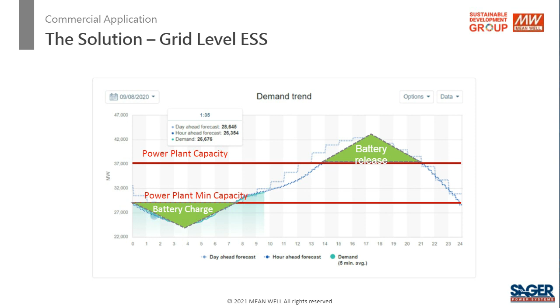During the power plant minimum capacity period, when energy is not used as much, it's able to charge the battery to refill it for the peak release during peak demand. There are two terms: the battery charging at the bottom is called valley filling, and at the peak, during release, that's called peak shaving.